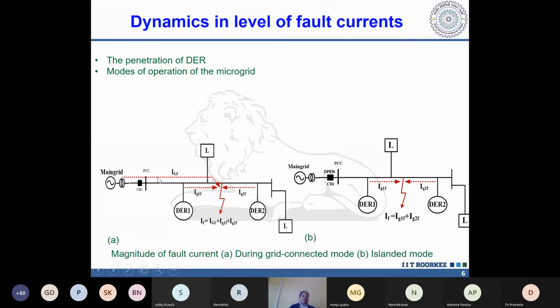That's why we have used IGF here. What is IGF? This is the fault current, where G stands for grid, main grid, and F stands for fault. So IGF is the main fault current contributed by the main grid to the fault point. Similarly, IG1F is the fault current contributed by DER1, and IG2F is the fault current contributed by DER2.